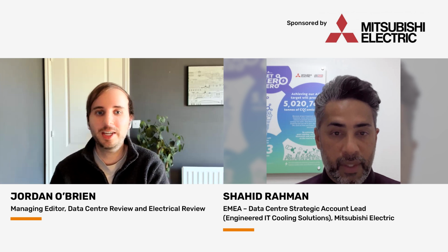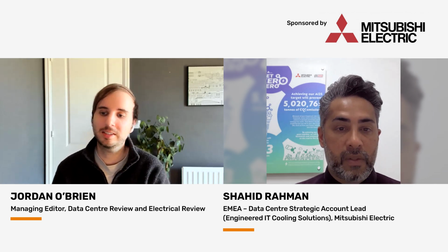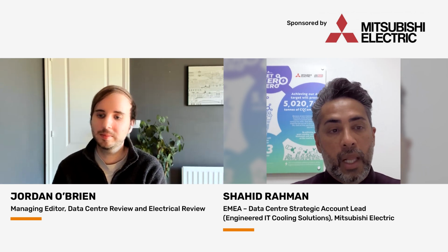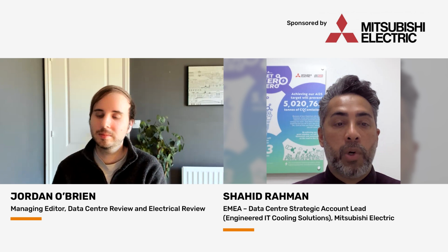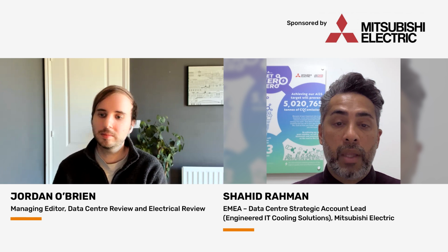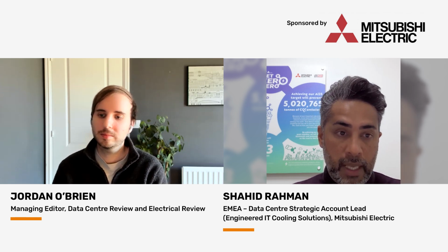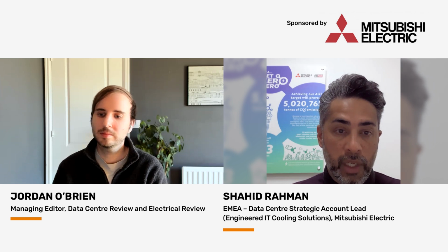How can heat pumps improve the energy efficiency and sustainability of data centers? That's a good question. It's not always practical or possible to connect district heat networks onto the heating networks, for example where the local heat requirement is not constant, but there are options for using rejected heat on site. Simultaneous heating and cooling chillers are particularly useful in data centers with coincidental heating and cooling loads - if the heat extracted from areas that require cooling can heat occupied spaces close to the data center, like the offices, that's really good.